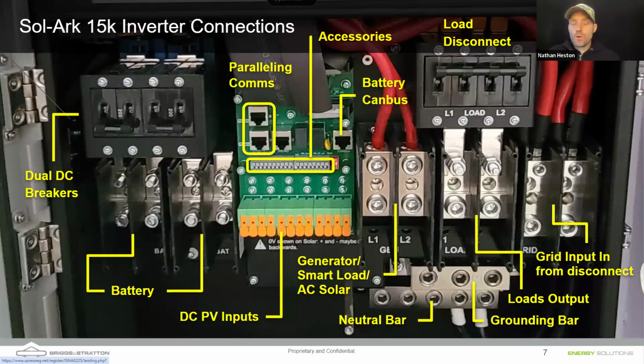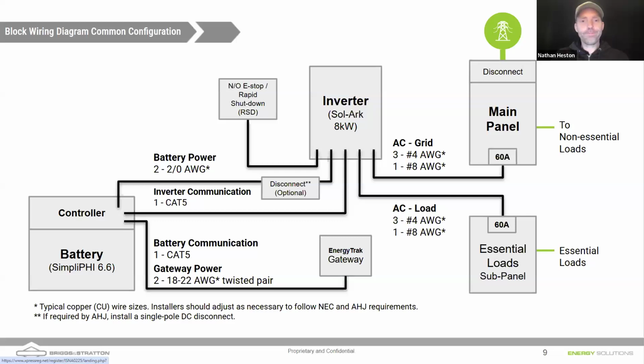The neutral bar, your grounding bar are there. The ground and neutral should be tied at your first point of service disconnect, which would be right before this inverter. You should have it on a breakered or at least a fused disconnect after your meter. And then you've got your grid input and your load output, and those are rated at 200 amps.